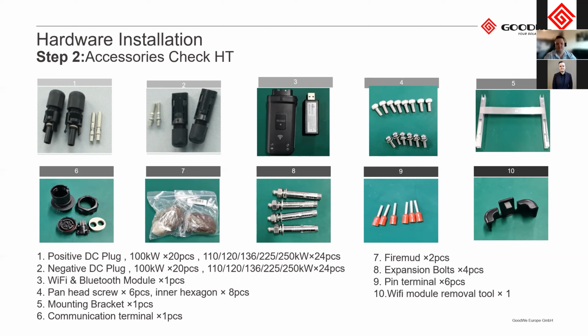The Bluetooth module as well, on the right-hand side of the Wi-Fi module on the page, you'll see that's our Bluetooth module. So if you just want to do a quick commissioning of your system, you can also hot swap the Bluetooth modules between the devices. That's not a standard Bluetooth module. You can't use any Bluetooth module on our device. You have to use our specific one. As I said, that port is not a standard USB port. It's just a USB kind of port that we're using for the connection.